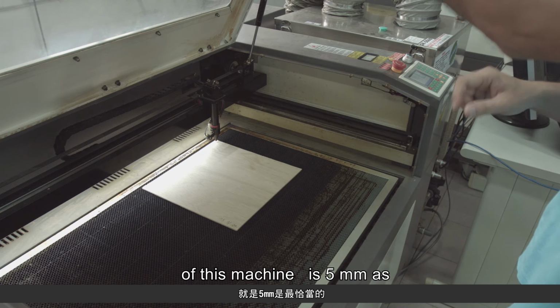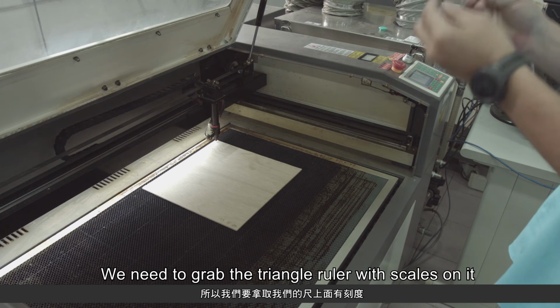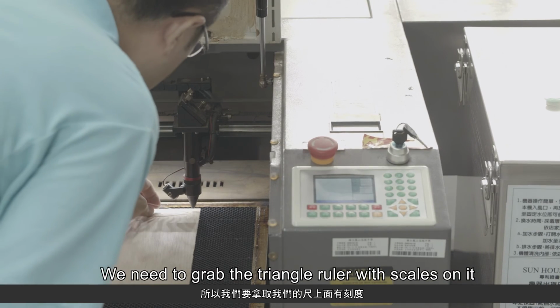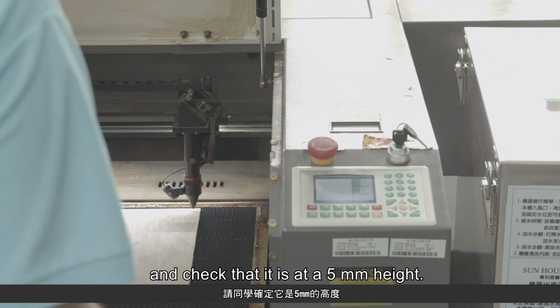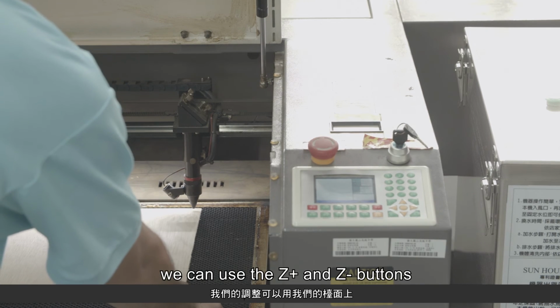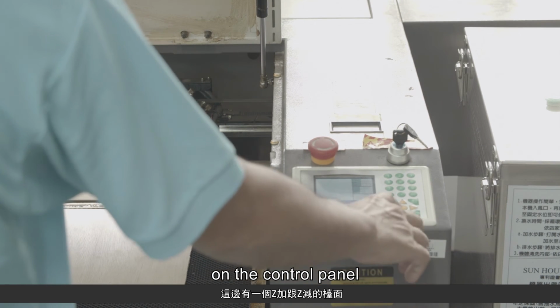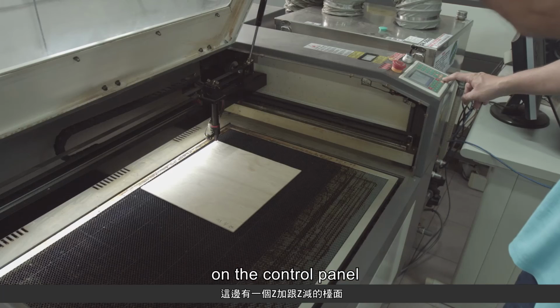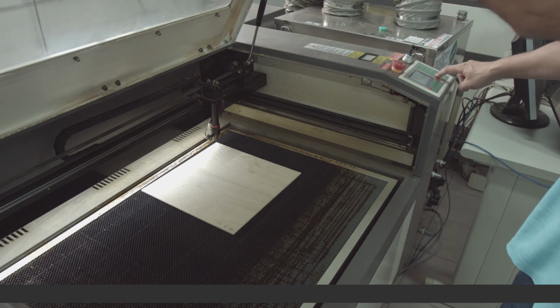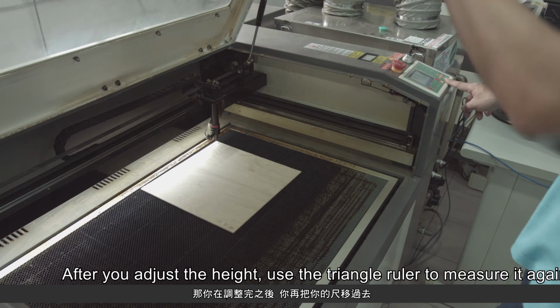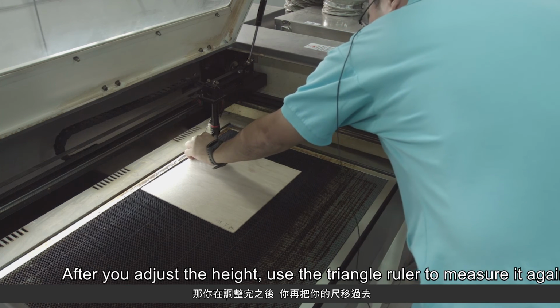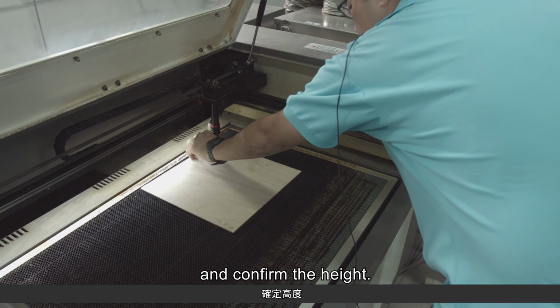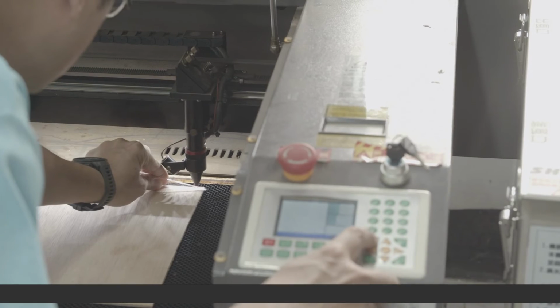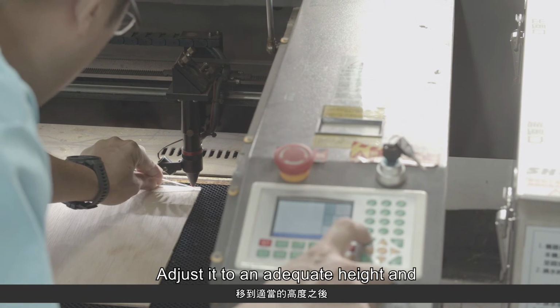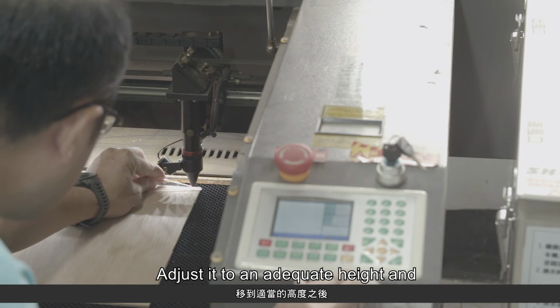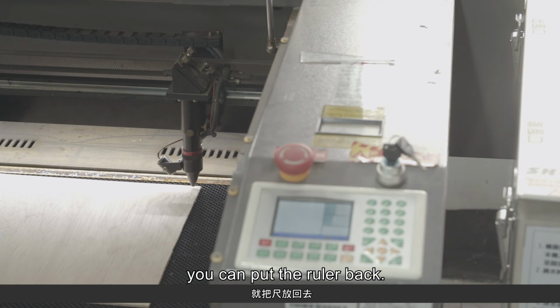As the most appropriate distance, we need to grab the triangle ruler with scales on it and check that it is at a 5 millimeter height. If it's not, we can use the Z plus and Z minus buttons on the control panel to adjust the height. After you adjust the height, use the triangle ruler to measure it again and confirm the height. Adjust it to an adequate height and you can put the ruler back.